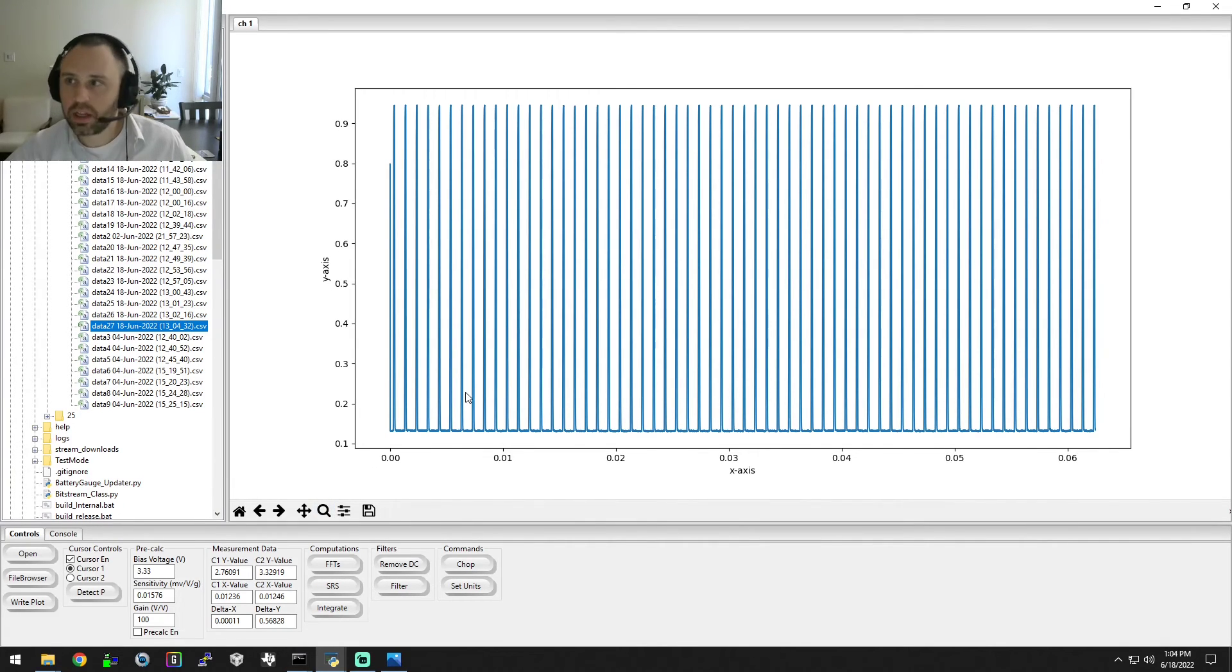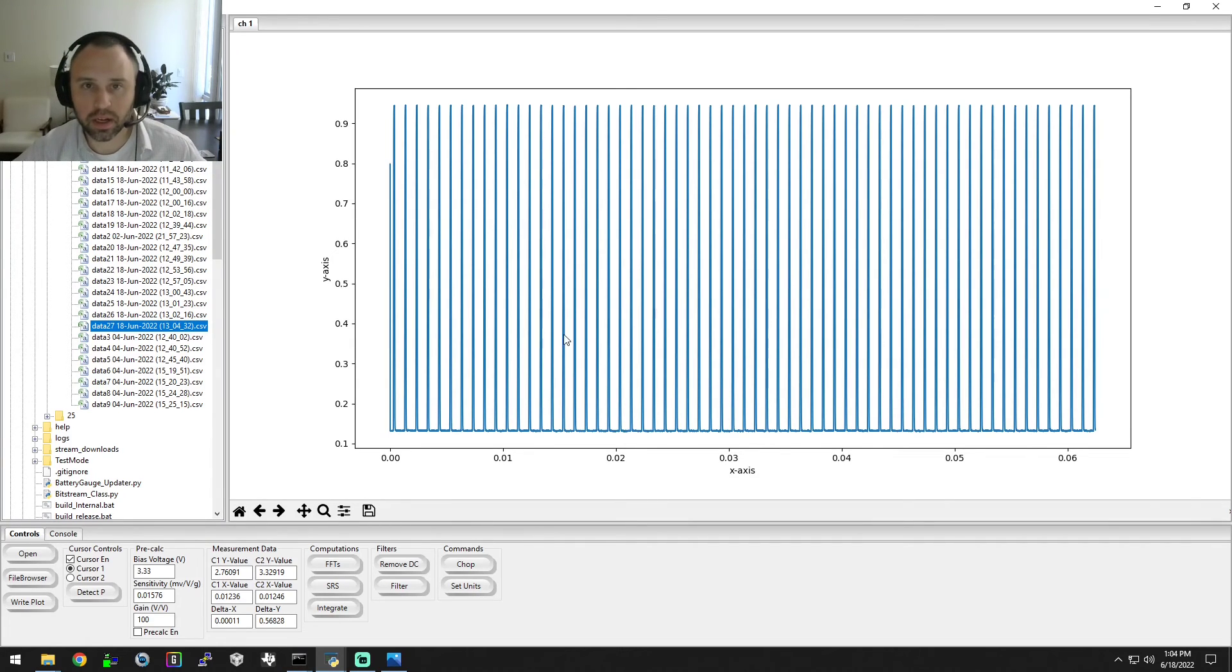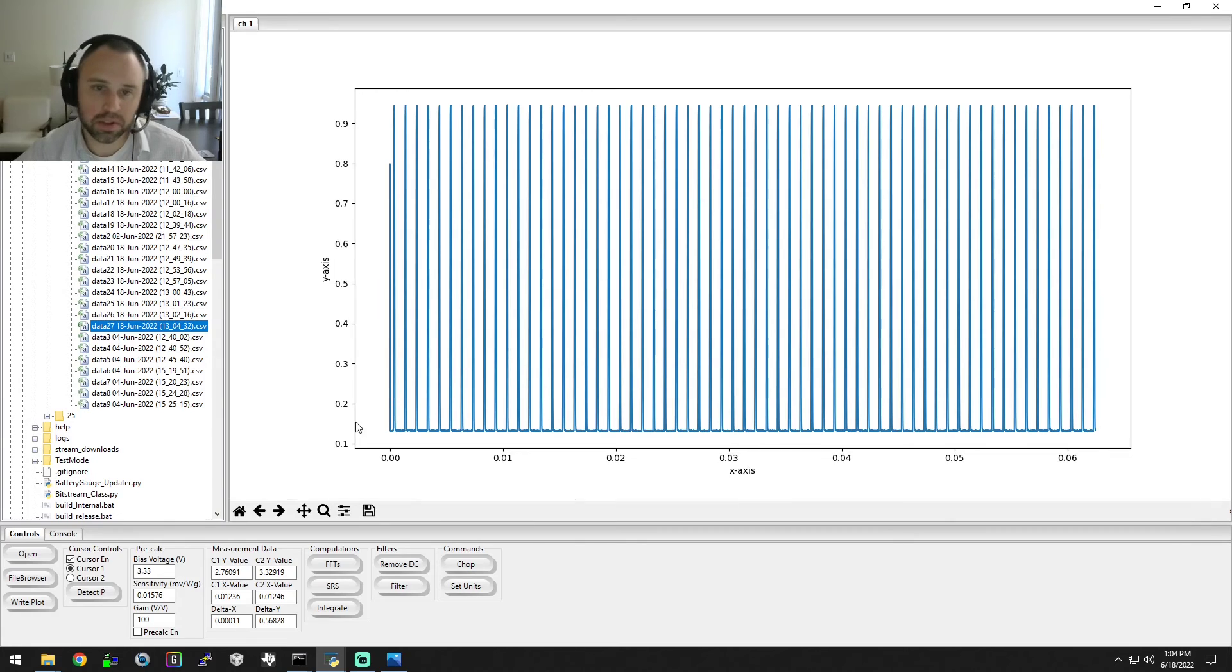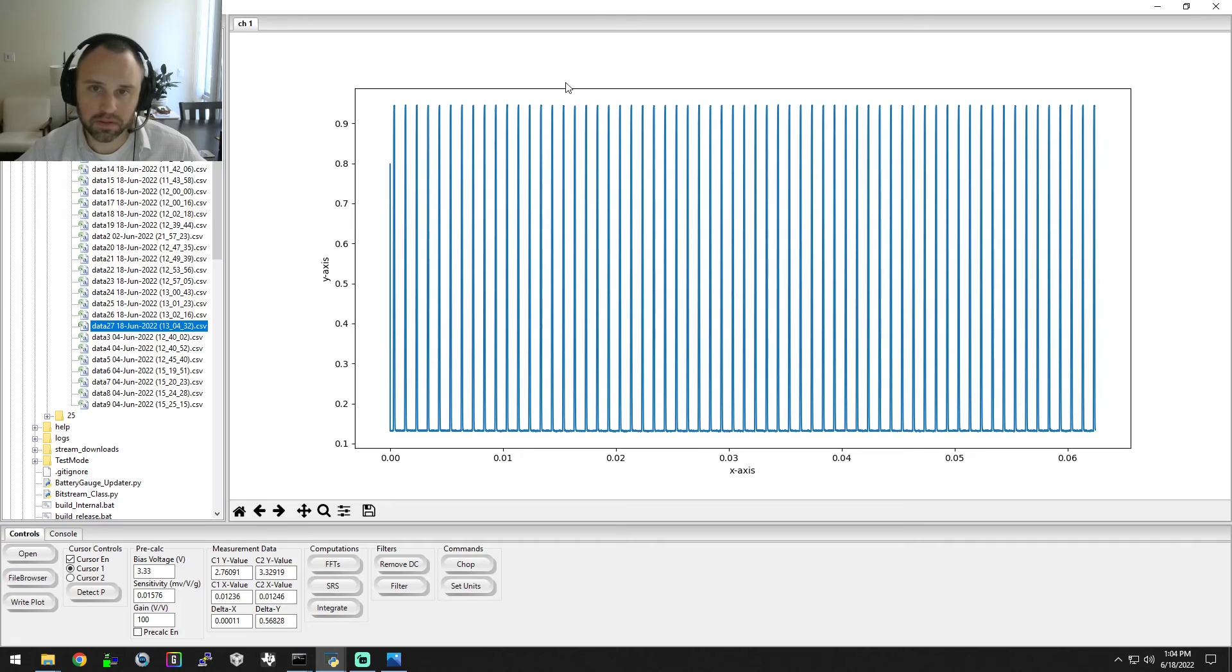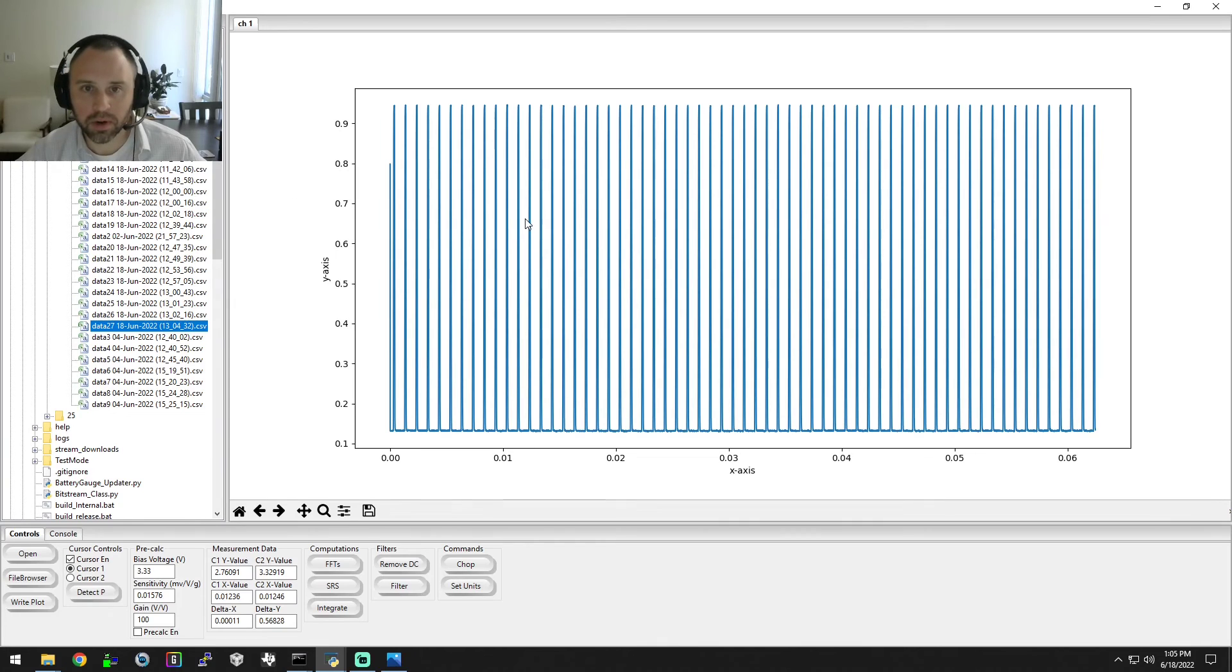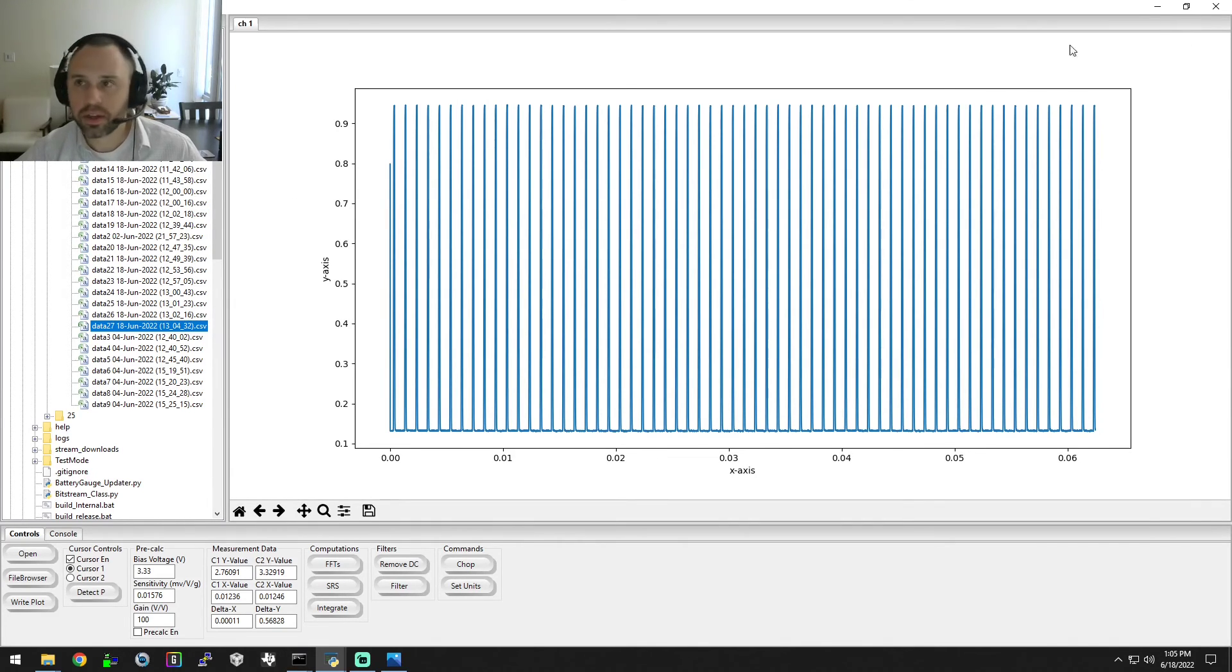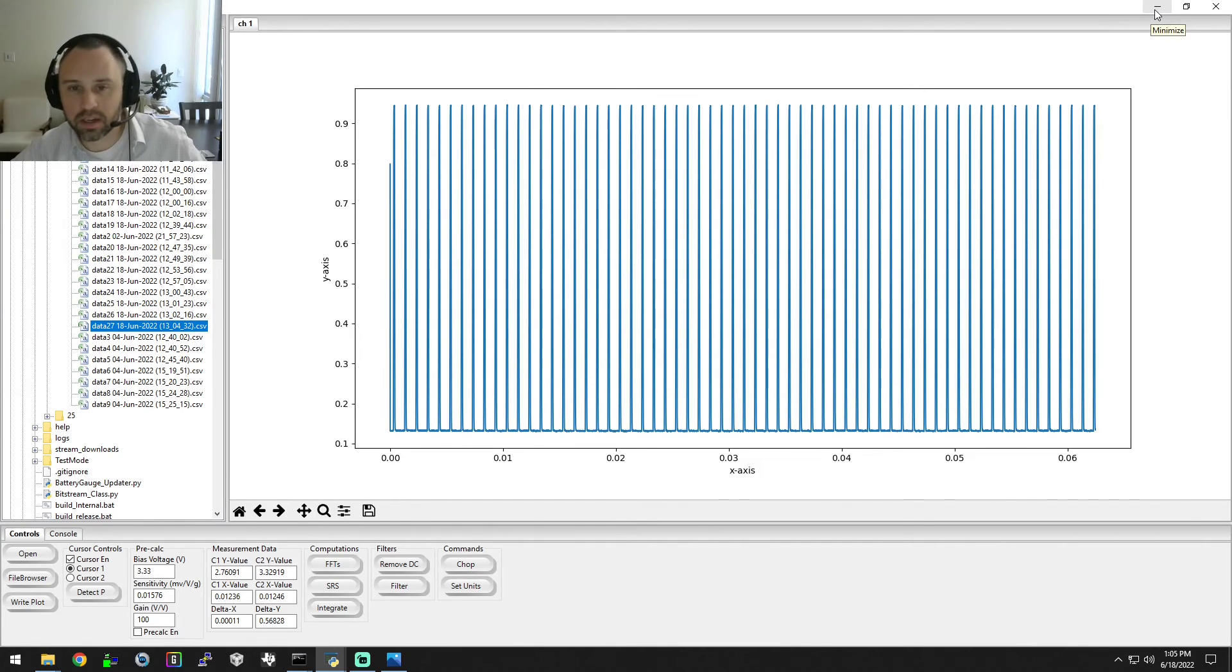File 27, and we can see we're right down approaching zero, so you really get full range in this product line. We're at 0.9 so there's plenty of headroom. If you had a sensor in this situation that had a lot of overshoot and very little undershoot, you can shift this waveform down and maximize the value in the instrument to the customer by maximizing the dynamic range. So that's pretty much it for this test.